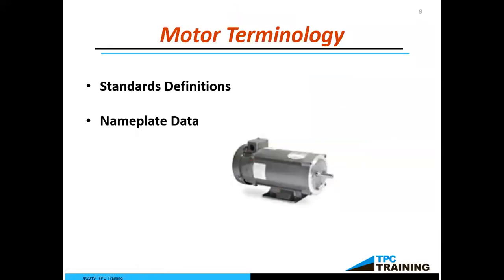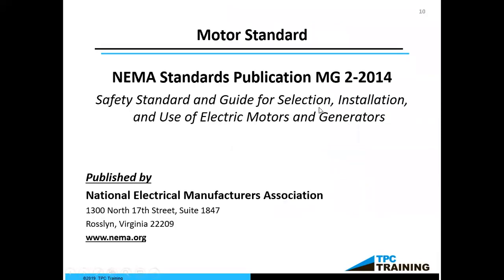So we're going to look a little bit at motor terminology and some standard definitions. All of this came out of a standard. And of course, we have lots of standards. ANSI comes up with standards. The NFPA comes up with standards, IEEE. Well, this standard came from NEMA, the National Electrical Manufacturers Association. And it is a standard and a guide to select, install, and use electric motors and generators. So it's the MG2 standard. It was revised in 2014. It can be purchased from NEMA. It has a lot of information on it, but all of the terminology that I'm about to pass on to you, you will see came from this standard. And I just wanted to let you know that it is out there.